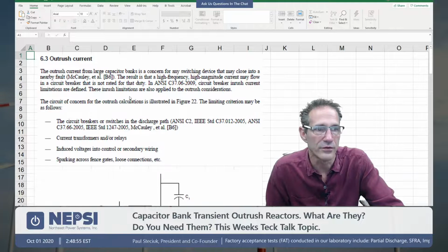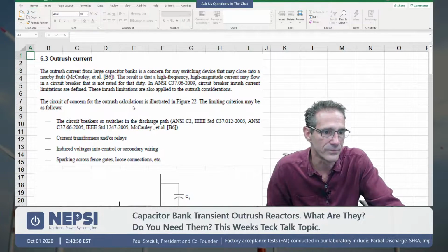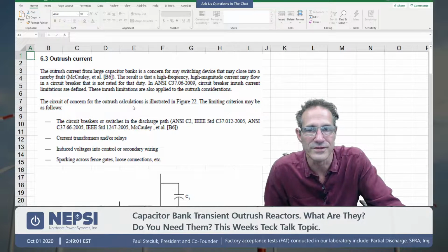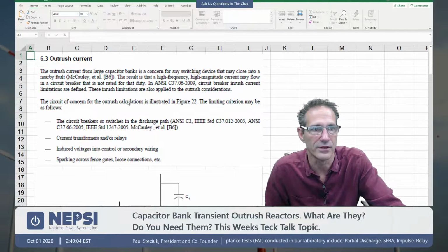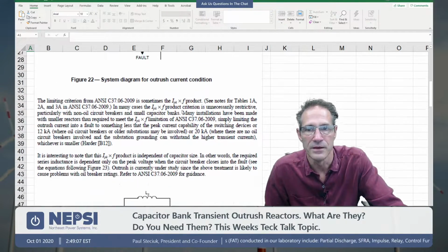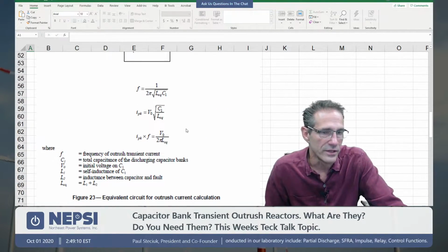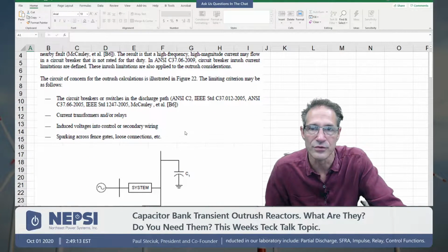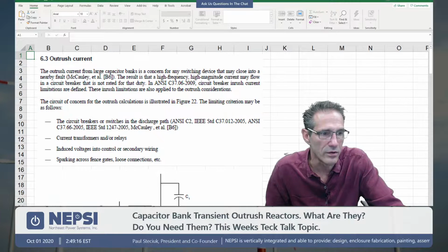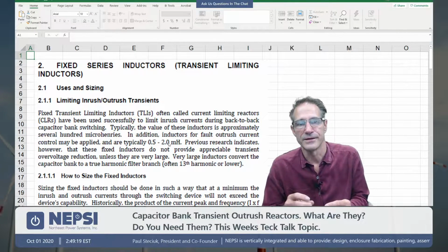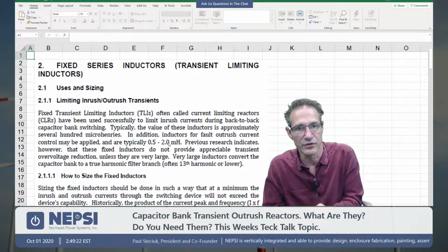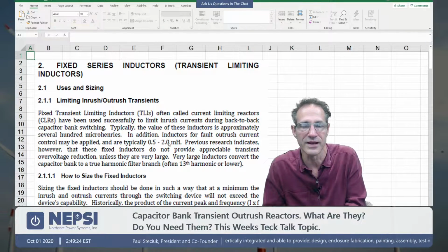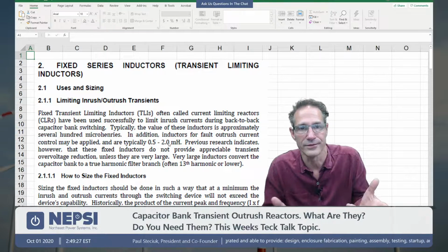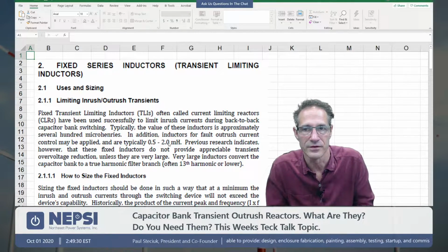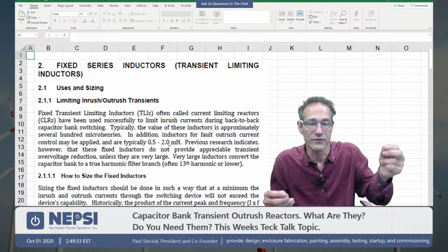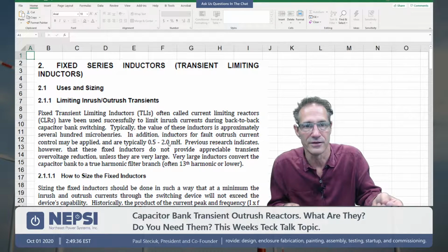There's also another standard that speaks to it, and that's C37.012, the 2010 standard. And it also talks about outrush current. And what's interesting about this note here is that there are situations where for very small capacitor banks, the frequency can get very high. So if you start looking at the I times F factor, if you have a very small bank, like say you have a surge capacitor of 0.5 microfarads, you can get a very high frequency, and it takes that IF factor sometimes beyond the breaker rating.